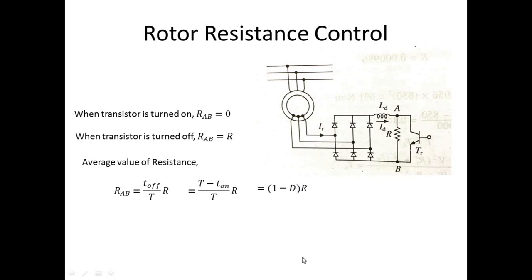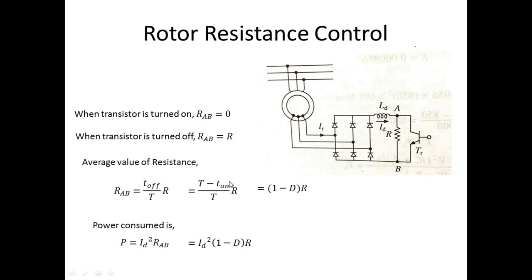There will be power consumption due to this resistance: P = I_D squared × R_AB, where R_AB = (1 − D) × R. This is the disadvantage of rotor resistance control — power is wasted. If duty ratio D is controlled from 0 to 1: when D = 1 (fully on), R_AB = 0; when D = 0, R_AB = R (maximum).